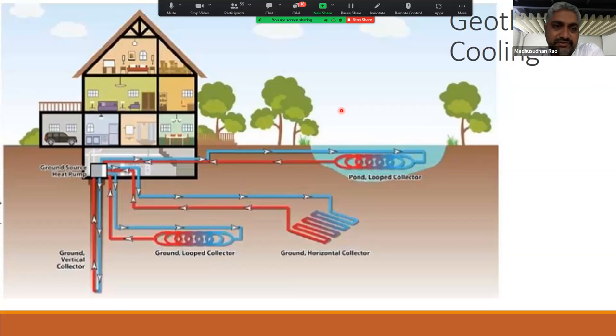So because of this, if you see in this picture that I'm showing, as I said earlier, cooling to me is a process of taking away the heat. And it's the same thing. Today, we reject the heat that is coming from indoors to air and call it air cooled. We reject it to a cooling tower and call it water cooled. We reject it to the ground in any of these different ways. You know, there are different heat exchangers, vertical bores, horizontal loops, or horizontal piping. And we call it ground source heat pump, or ground as a heat sink or heat exchanger.